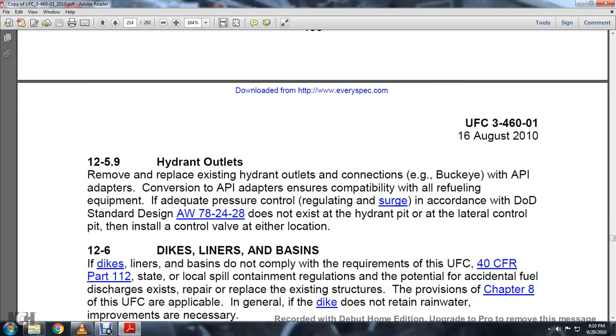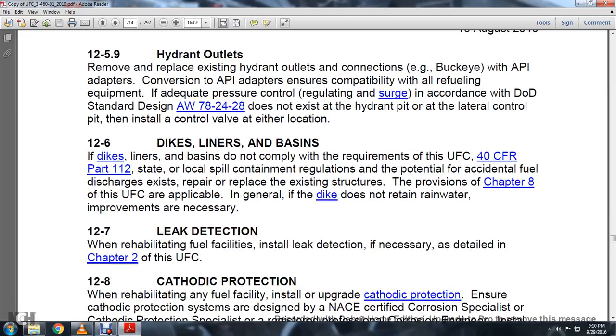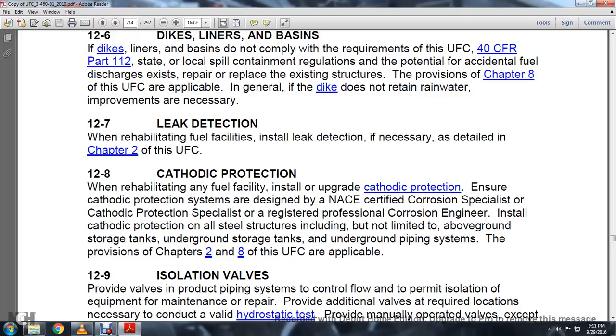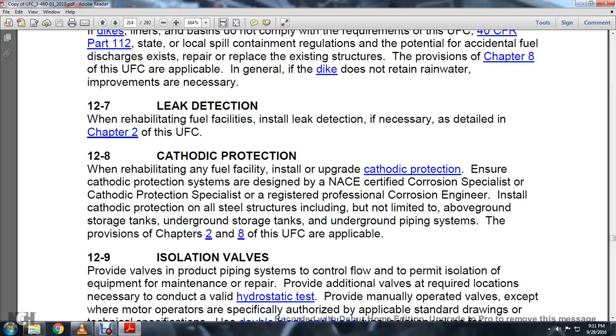Install control valves in the hydrant pit or lateral control location as appropriate. Section 12-6: Dike and basin liners. Comply with requirements of the UFC, Title 40 Part 112, and applicable state and local spill containment regulations. Evaluate the potential for accidental fuel discharge from existing structures and repair or replace as necessary per Chapter 8 of the UFC. Ensure dikes do not retain rainwater. Improve leak detection as necessary when rehabilitating fuel facilities. Section 12-8: Cathodic protection rehabilitation. Any facility installing or upgrading cathodic protection must ensure the design is performed by a NACE-certified corrosion specialist, cathodic protection specialist, or registered professional corrosion engineer. Install cathodic protection on all structures including above-ground storage tanks, underground storage tanks, and underground piping systems. Provisions of Chapters 2 and 8 are applicable.